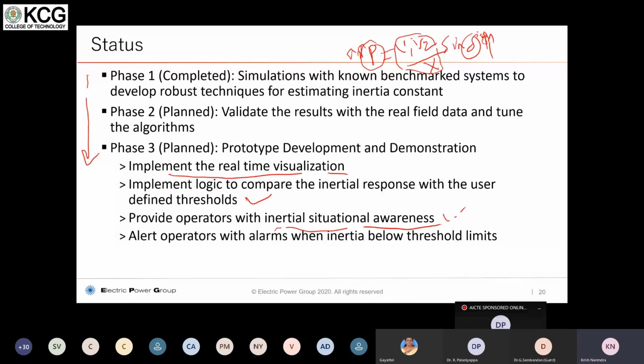So what I'm trying to analyze here is that the situational awareness for the current systems is measured directly by the phase angle measurement that we are doing through the synchrophasor. In a very similar manner, the inertial situational awareness can also be plotted similar to this power equation. We can evaluate the H inertia of the system continuously, and the operator can look at the situational awareness of the inertia. That's what we are trying to do in the third phase, basically, to alert the operators with alarms when the inertia goes below certain threshold limits.